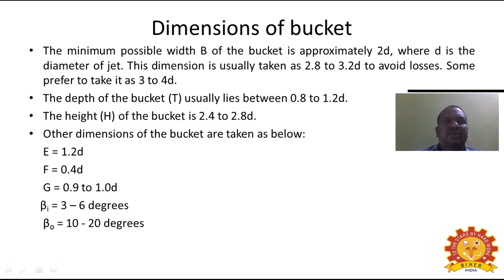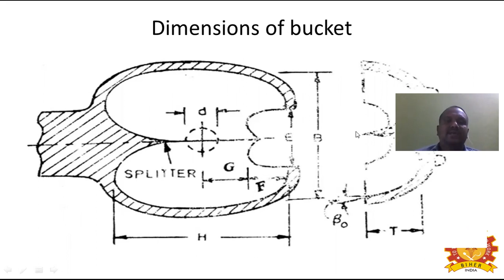Other dimensions of the bucket are taken as below. Capital E is 1.2 D, F is equal to 0.4 small d, G is equal to 0.9 to 1.0 D, beta is equal to 3 to 6 degrees, beta 10 to 20 degrees. The dimensions of the bucket, center splitter, and diameter are shown in the diagram. The number of buckets decides the frictional losses, the velocity of water, and the impact of kinetic energy on the wheel.